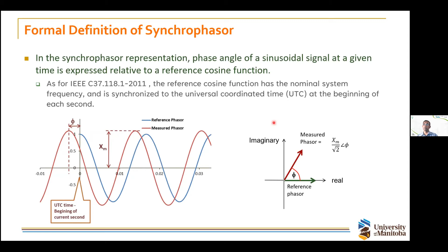So if we use the internal clock of each device to generate the reference signal, then when you calculate the phase angle, they are not with respect to a common reference. That is why we need to adhere to UTC, which is the standard time, or the absolute time reference.